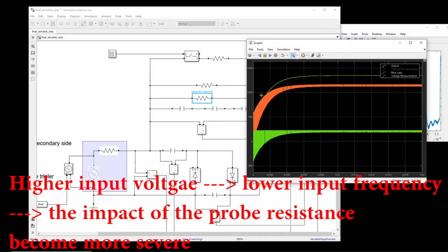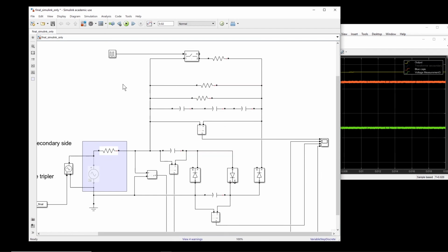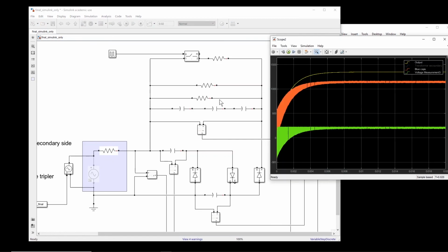But actually in this simulation it shows that the voltage drop is not significant, so even a 10 megaohm probe will show more or less the final value. So if your probe has maybe 1 gigaohm input impedance -- a high voltage probe usually has 1 gigaohm -- then you can measure this very accurately.